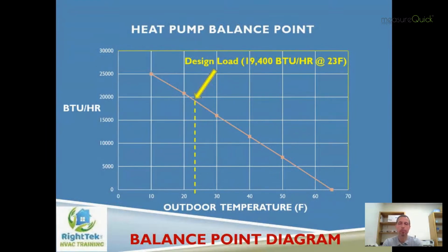Basically, in the center of this chart, if you look at the orange line, my load, the 19,400, was at a design outdoor winter temp of 23 degrees. So I find my 19,400 at 23 degrees. I drop a pencil point. That's where you see the yellow arrow there. And I make a straight line down that chart from 65 degrees at 0 BTUs per hour. That's considered to be the point of no heat loss.